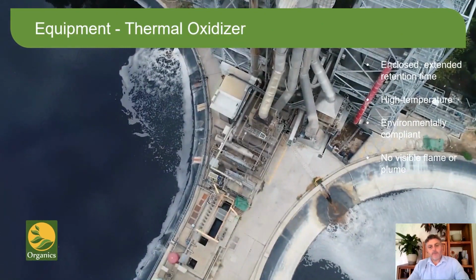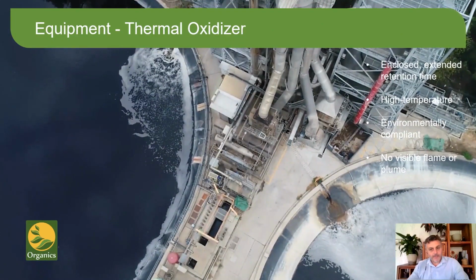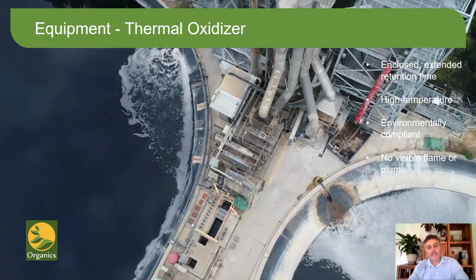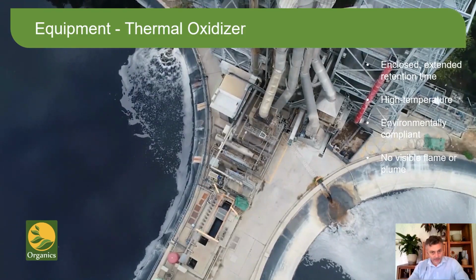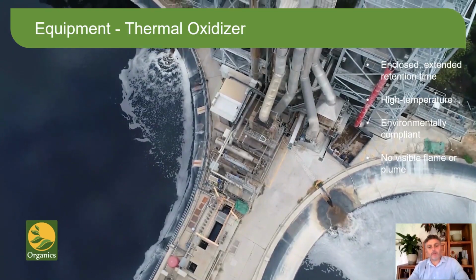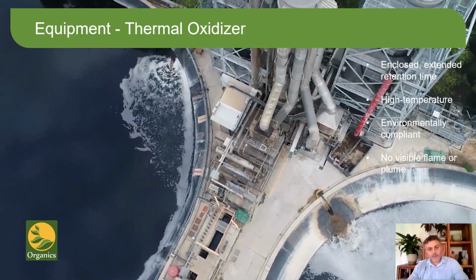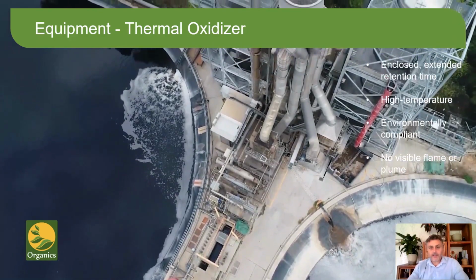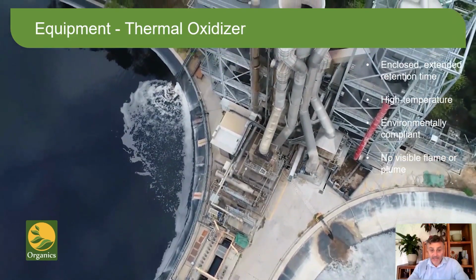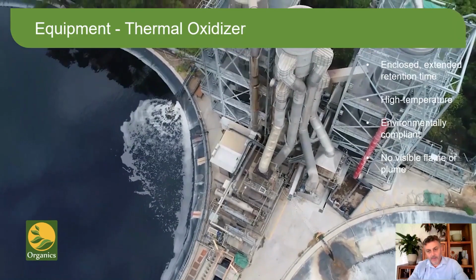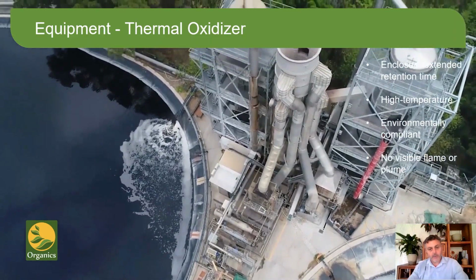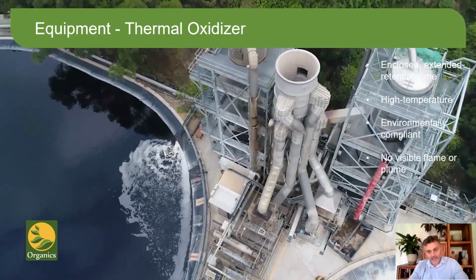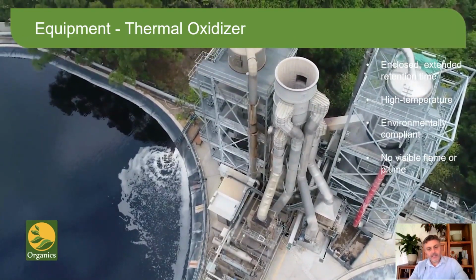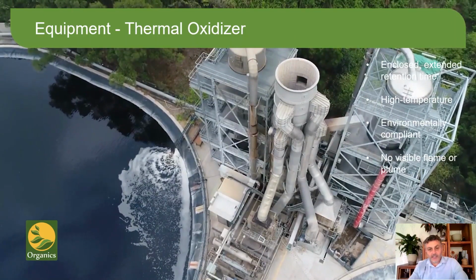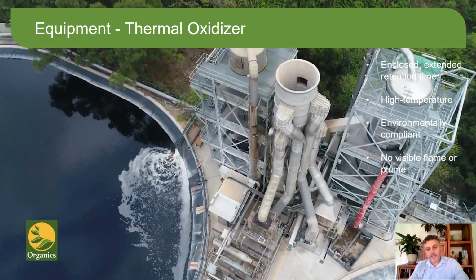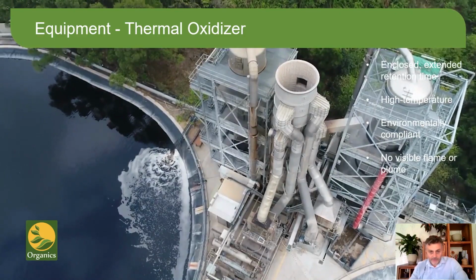So let's have a look at the major components that make up a typical plant. It's a thermal process that relies on heat, so let's start with the source of the heat, the thermal destructor, or as it is sometimes called, the thermal oxidizer. The thermal destructors that we use are our own design, based on our 30+ years of experience in landfill gas flares. They share the same burner cup design that our landfill gas flares use, which ensures correct mixing of primary air and keeps the burn stable, but have additional features that have been introduced specifically to deal with the particular issues surrounding emission control that combustion of ammonia introduces.